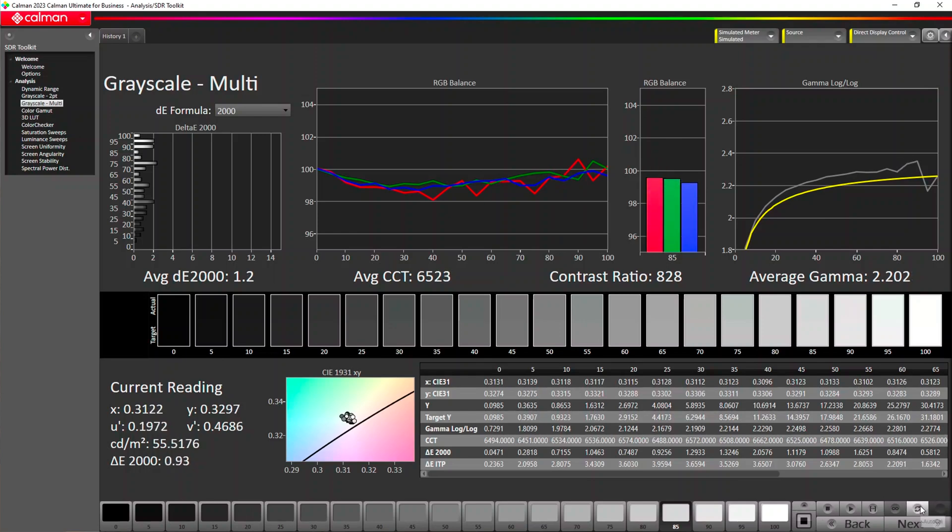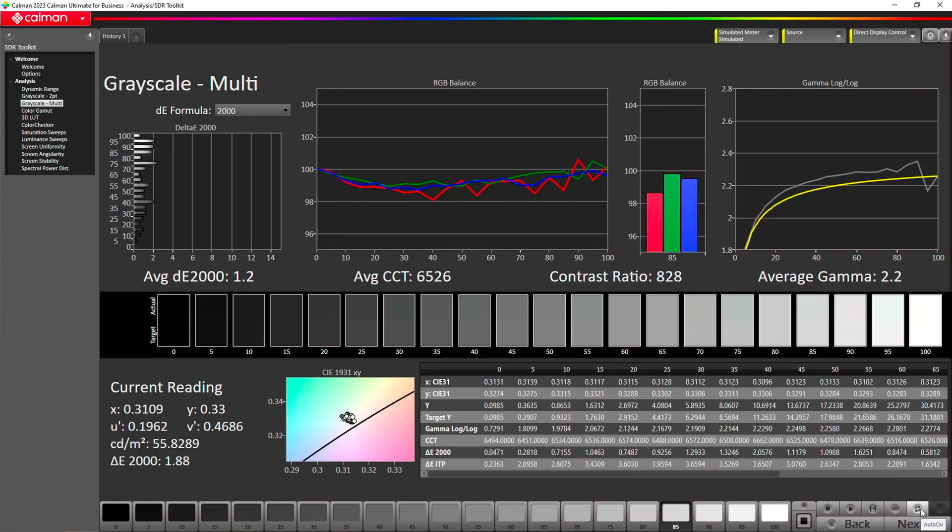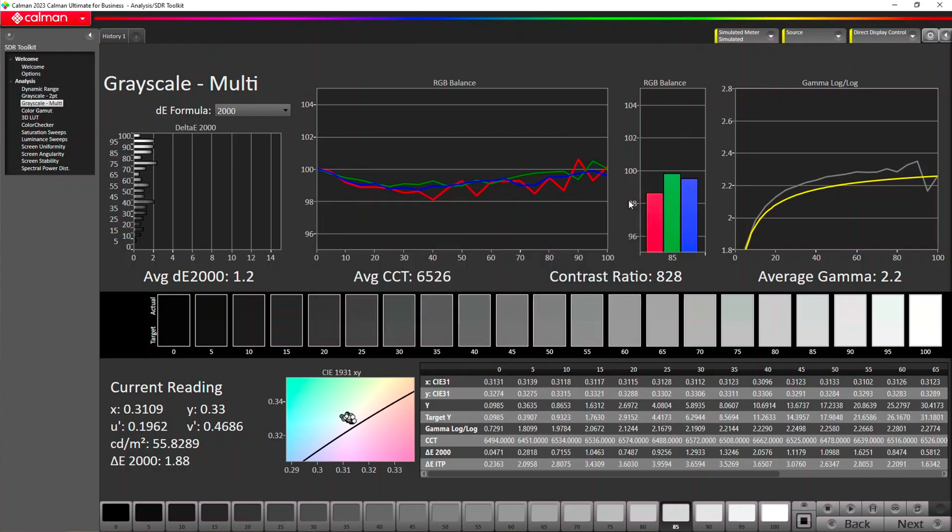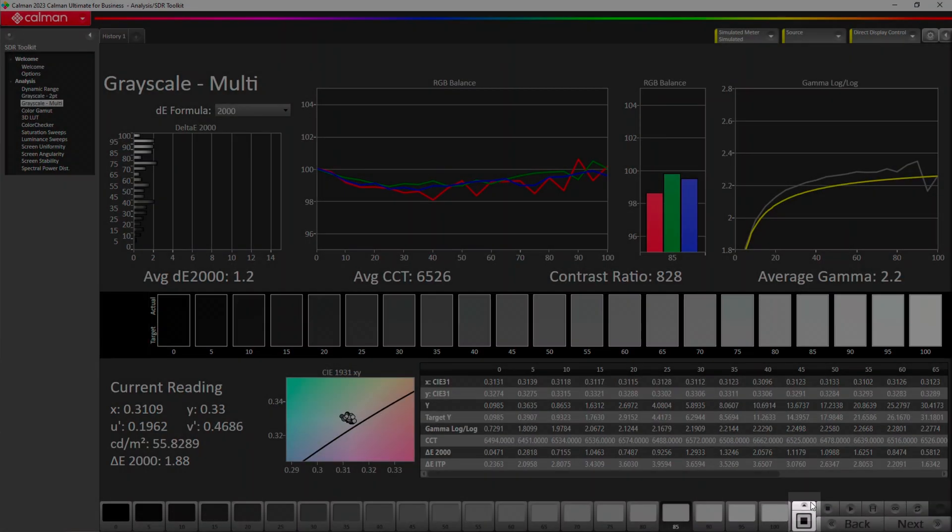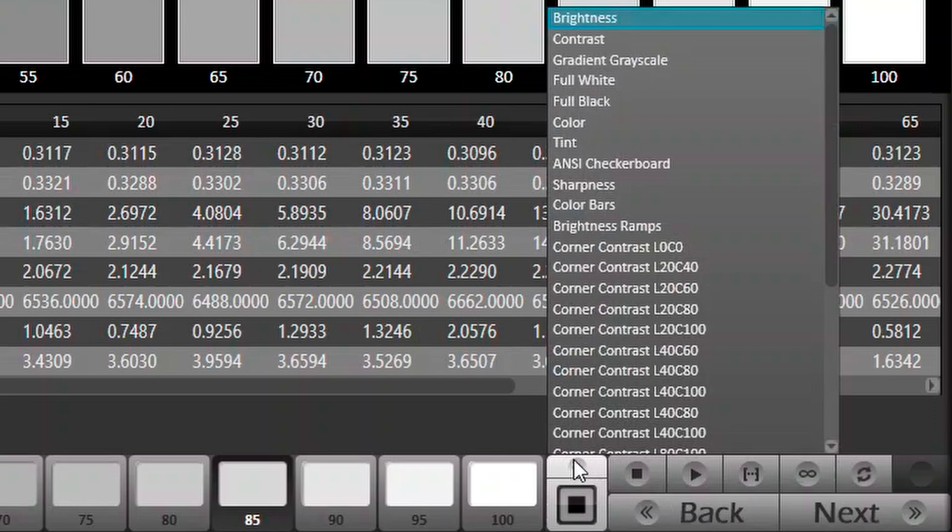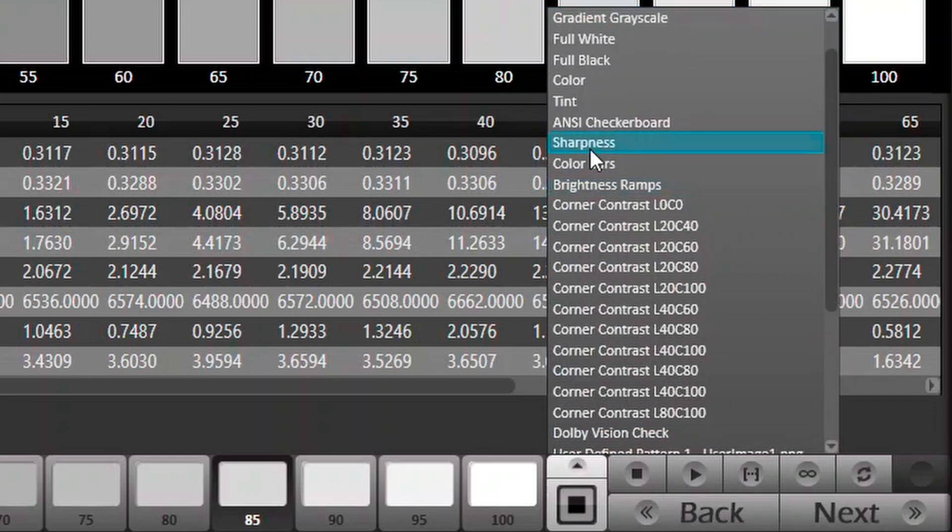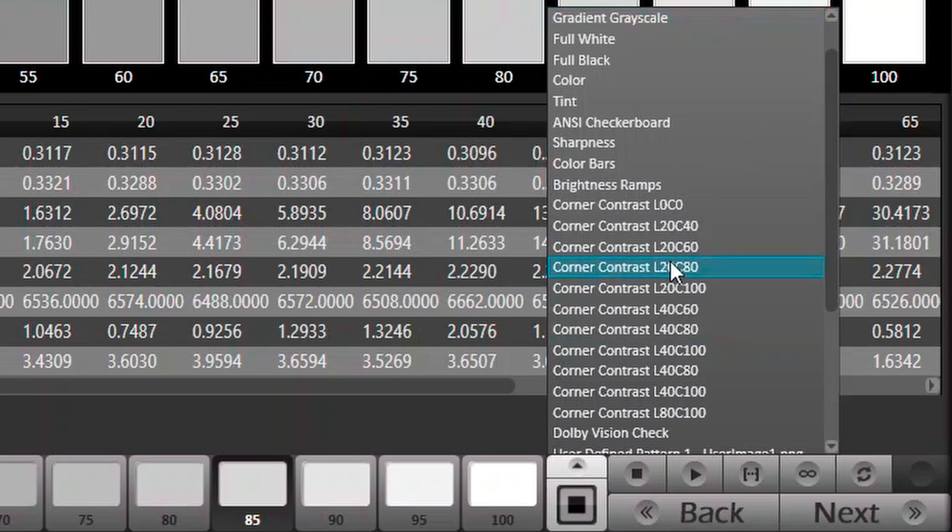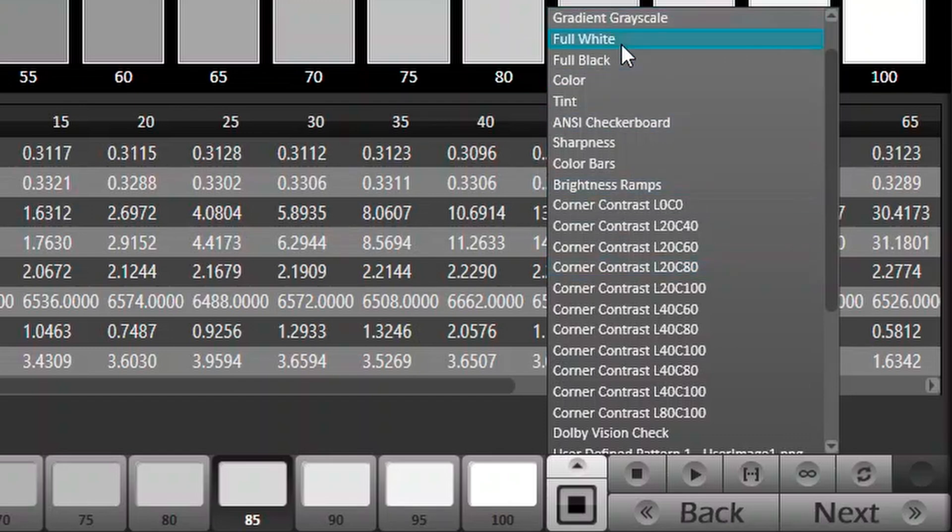And then the last button over here that's active is our AutoCal button. The AutoCal button right now won't do anything because I'm not connected to any real hardware. If I was connected to a device, then it'd give me an option to start an automated calibration. I already did mention our back and next buttons. One other button I did want to mention down here was our specialty patterns button. This specialty patterns button allows us to bring up different test patterns. What shows up in this list will vary depending on what you're connected to. If you're connected to a specific generator, the specialty patterns list will be gated based on what's actually on that generator. So that's where you can find, you can go in and load up things like color bar patterns or contrast ratio boxes or something like that, depending on what you're looking at.